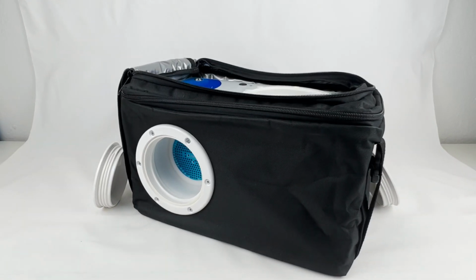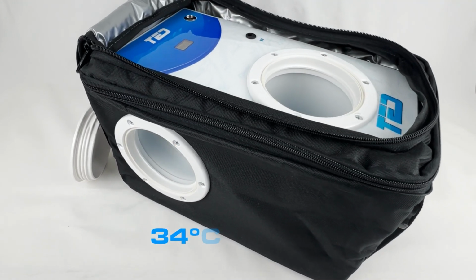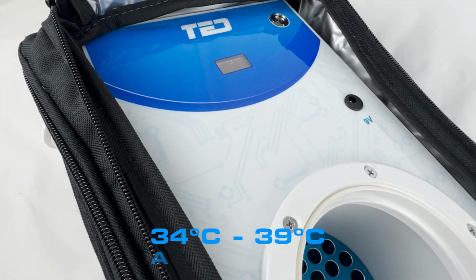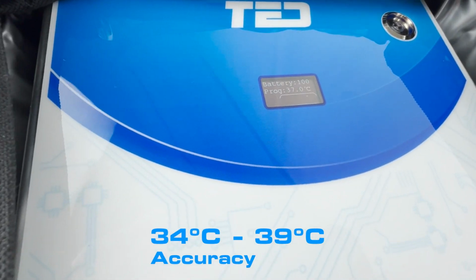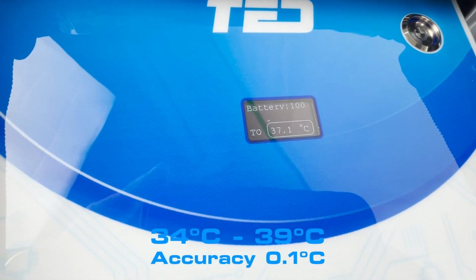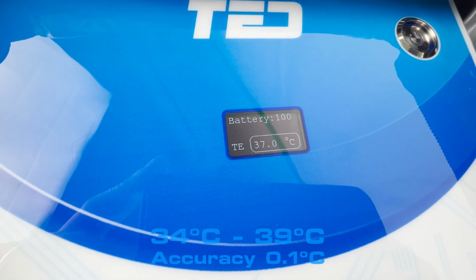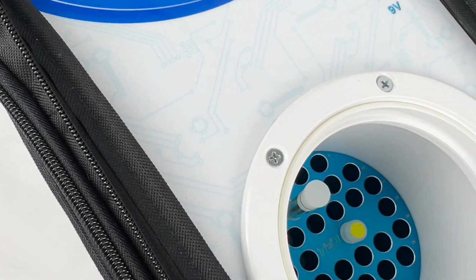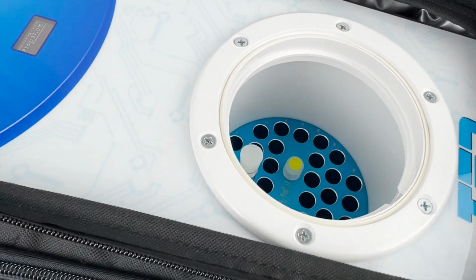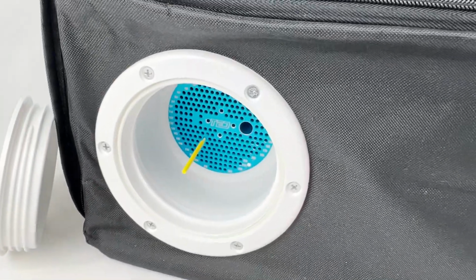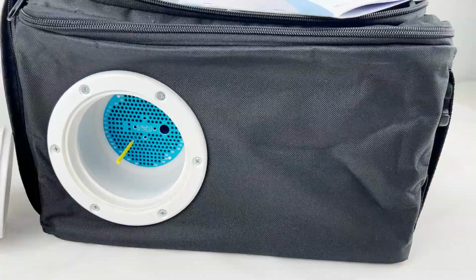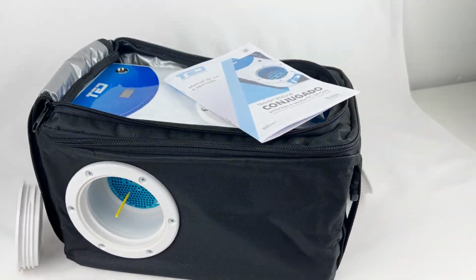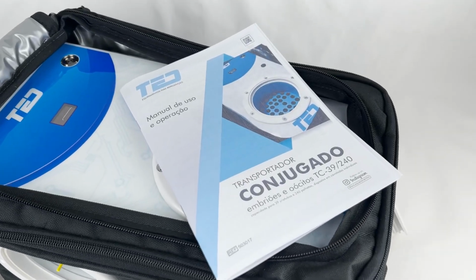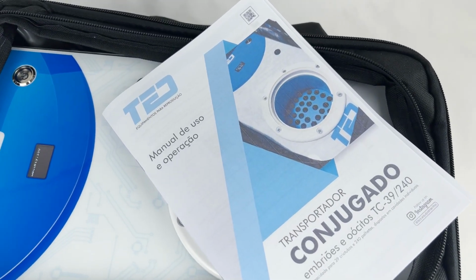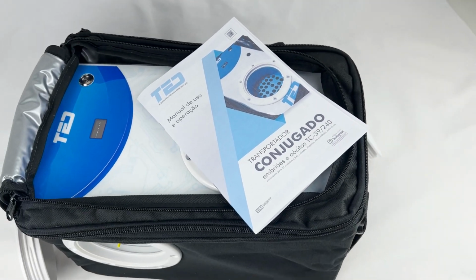The incubator is designed to maintain a constant temperature between 34 Celsius degree and 39 Celsius degree with an accuracy of 0.1 Celsius degree in a user-specified setting. Remember, transport cryotubes with caps or stoppers and sealed straws, or using sealers. In addition to the equipment, a user manual is provided detailing all the features, general operation, maintenance, troubleshooting, and warranty.